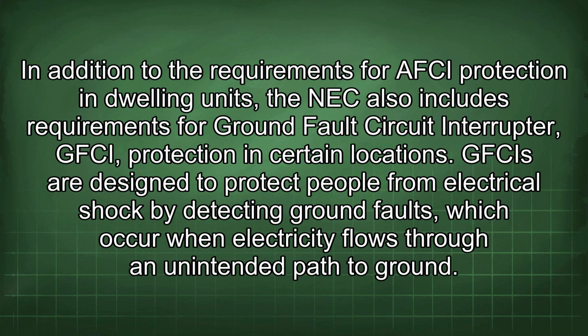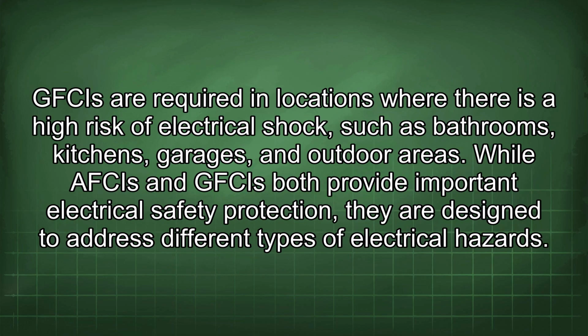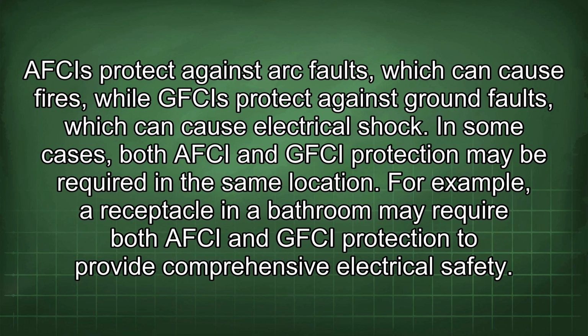In addition to the requirements for AFCI protection in dwelling units, the NEC also includes requirements for ground fault circuit interrupter (GFCI) protection in certain locations. GFCIs are designed to protect people from electrical shock by detecting ground faults, which occur when electricity flows through an unintended path to ground. GFCIs are required in locations where there is a high risk of electrical shock, such as bathrooms, kitchens, garages, and outdoor areas. While AFCIs and GFCIs both provide important electrical safety protection, they are designed to address different types of electrical hazards. AFCIs protect against arc faults, which can cause fires, while GFCIs protect against ground faults, which can cause electrical shock.